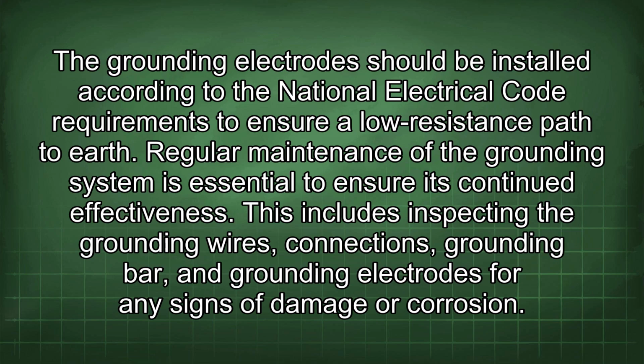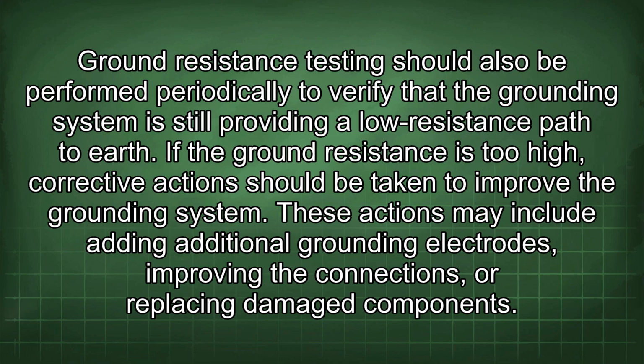This includes inspecting the grounding wires, connections, grounding bar, and grounding electrodes for any signs of damage or corrosion. Ground resistance testing should also be performed periodically to verify that the grounding system is still providing a low resistance path to earth. If the ground resistance is too high, corrective actions should be taken to improve the grounding system. These actions may include adding additional grounding electrodes, improving the connections, or replacing damaged components.